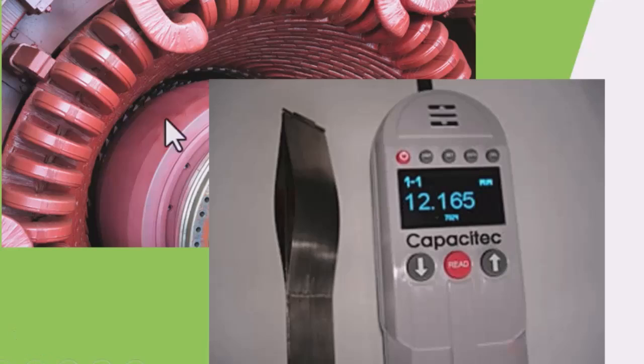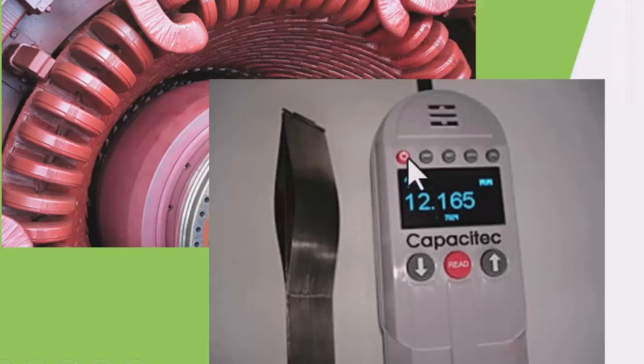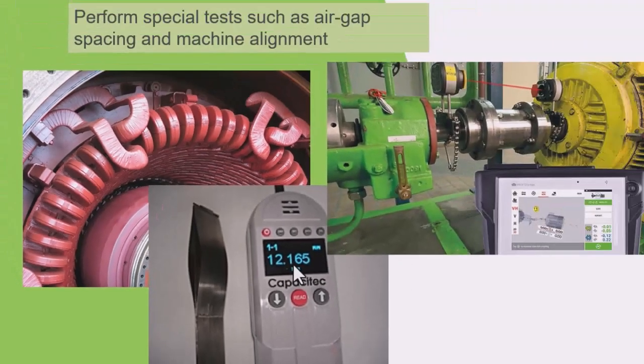So we can use test equipment like this. As we insert it, the spacing in millimeters of the space between the rotor and the stator will be registered in the equipment. So we use this air gap measurement device to determine that we have a uniform air gap around the electric motor or the generator.